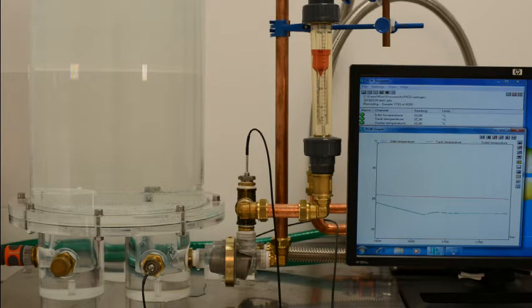So at the moment the red line is higher than the green and the blue line, because the tank temperature is higher than the inlet temperature, which means that the valve is completely bypassing the flow, so the inlet and the outlet temperature at the moment are the same. That's why the blue line and the green line are completely overlapping.